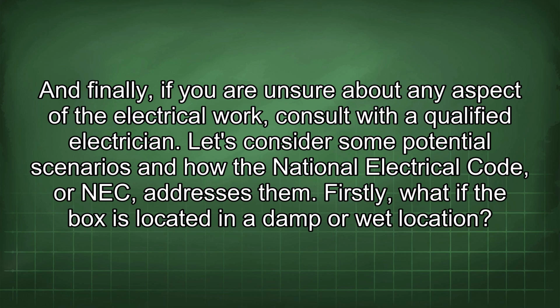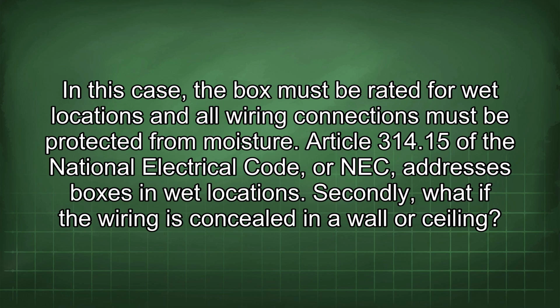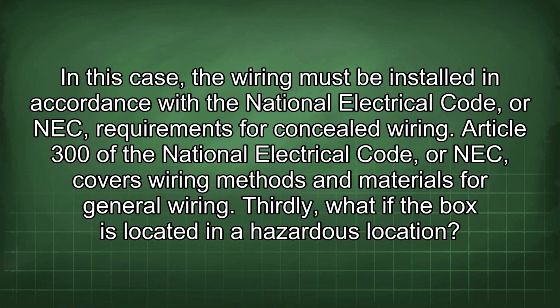Let's consider some potential scenarios and how the National Electrical Code, or NEC, addresses them. Firstly, what if the box is located in a damp or wet location? In this case, the box must be rated for wet locations and all wiring connections must be protected from moisture. Article 314.15 of the National Electrical Code, or NEC, addresses boxes in wet locations. Secondly, what if the wiring is concealed in a wall or ceiling? In this case, the wiring must be installed in accordance with the National Electrical Code, or NEC, requirements for concealed wiring. Article 300 of the National Electrical Code, or NEC, covers wiring methods and materials for general wiring.